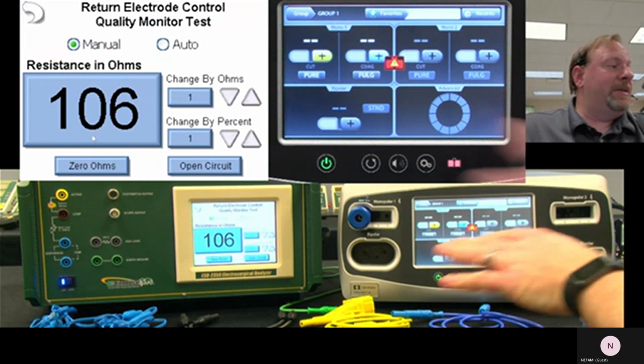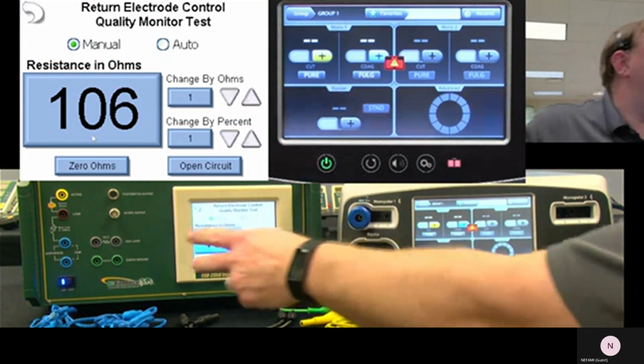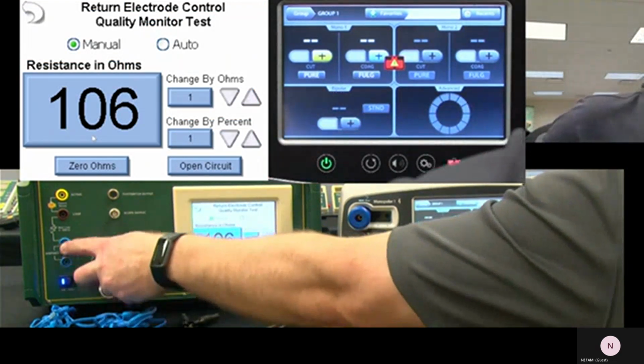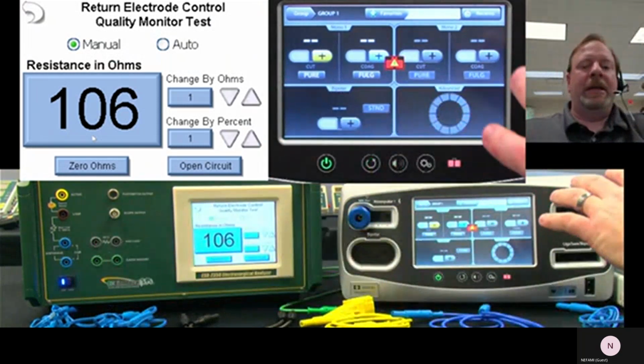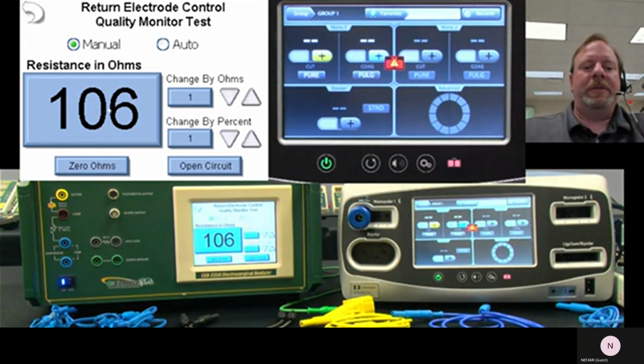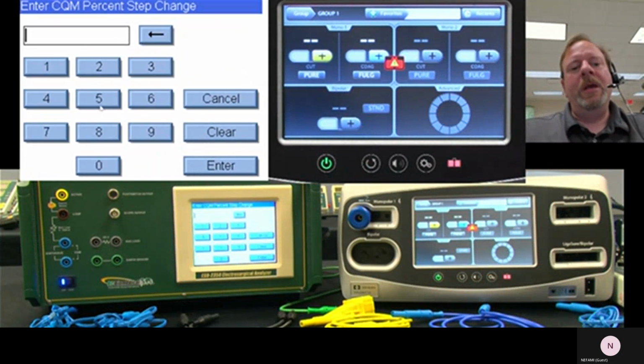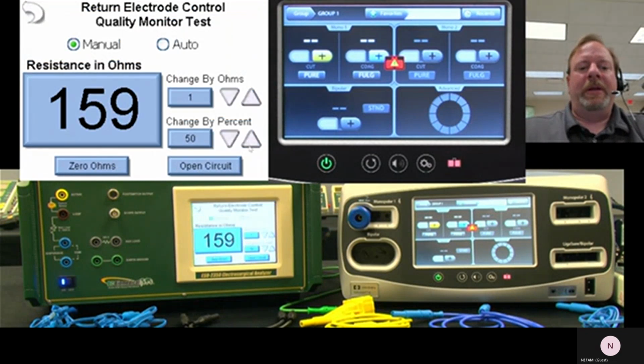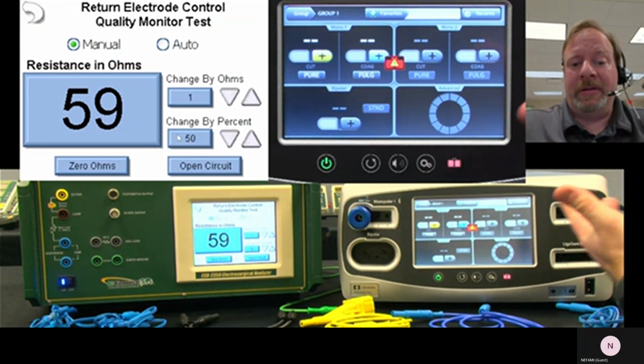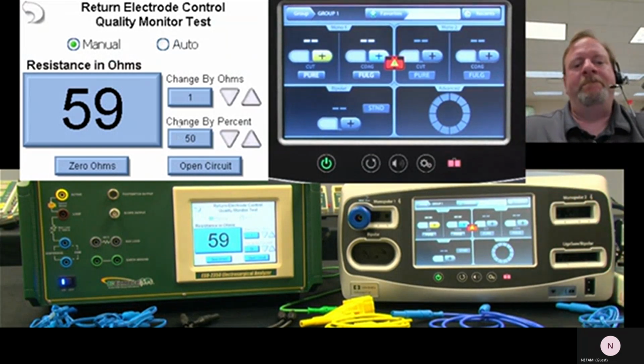And now this is a different load. And also it is here across the CQM. In this case, it is in single ohms. So we have a separate load bank than our power load. So we can adjust by a percentage. We can increase by 50%. A lot of the service manuals say if your resistance goes up 20 or 30%, you should get an alarm. So it makes it easy to test that.